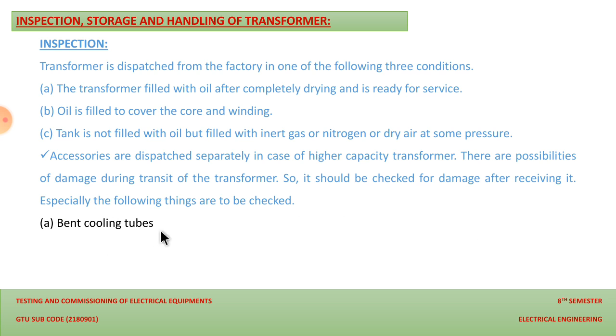So these are the things that you have to check. First is bent cooling tubes. Check the cooling tubes, whether they are bent during the transit. If they are bent, then it is very dangerous for the transformer if we use this transformer for our industrial purpose.